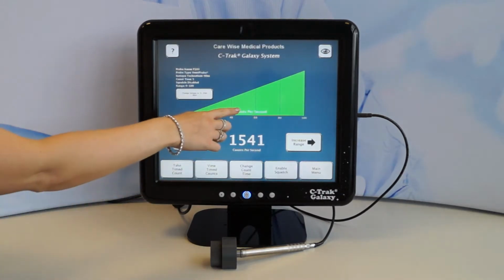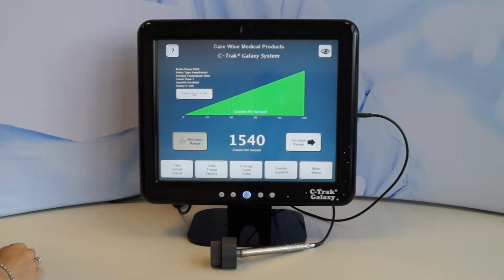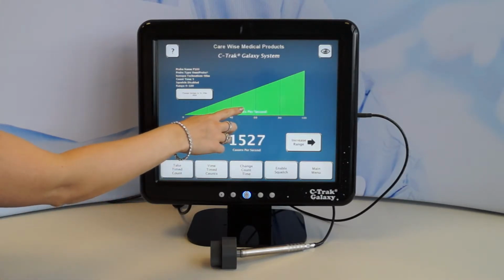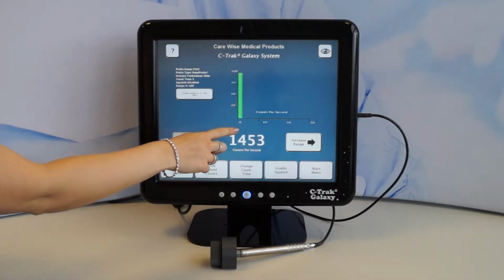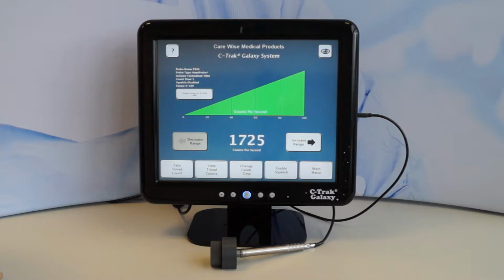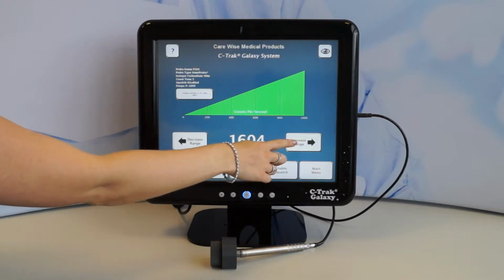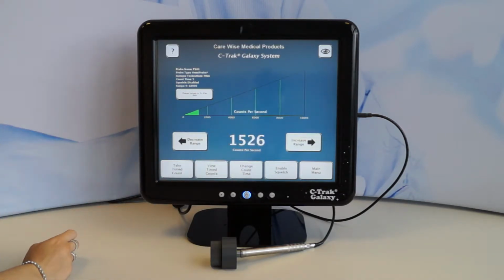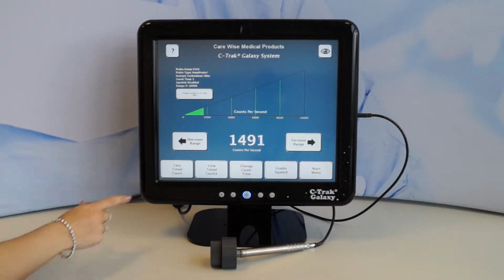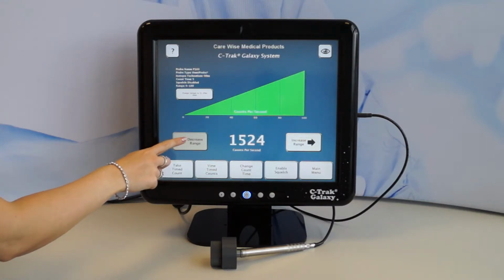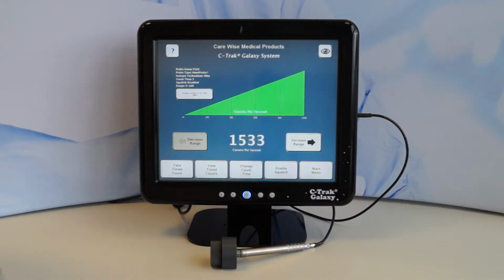The rate meter display in the centre of the screen gives a visual indication of the amount of radiation detected. You can change this display by clicking on the screen to show an analogue display or a counts per second over time. If the amount of radiation detected exceeds the scale, you may wish to increase the range. This changes the pitch to help the surgeon use the noise to locate the hot spot, but it does not change the true counts on the screen. You have an option of 0 to 100, 0 to 1000, 0 to 10,000 and 0 to 100,000. It is likely that you will only really need to use the first two scales during a procedure.